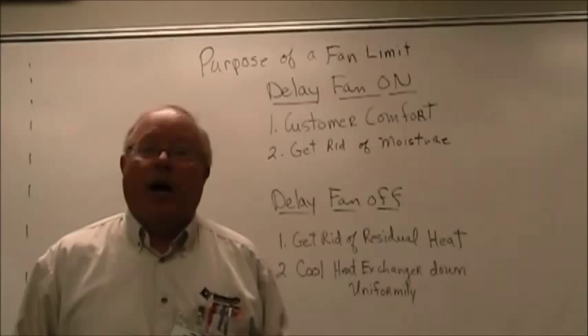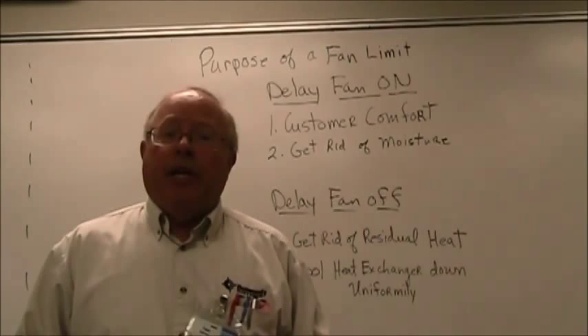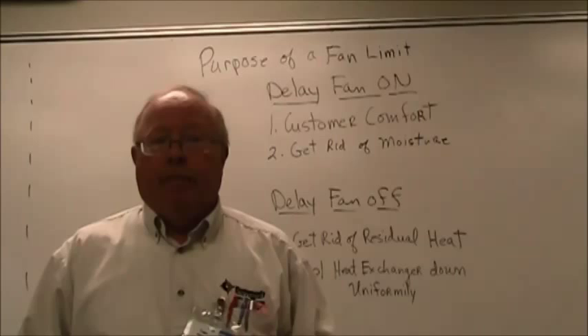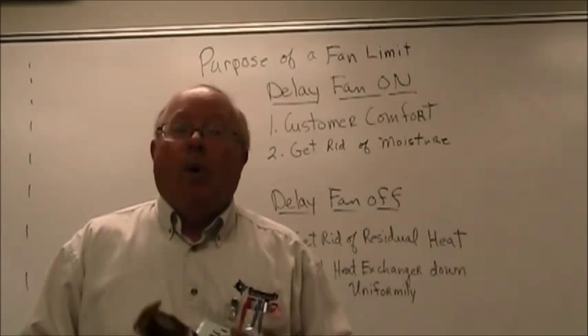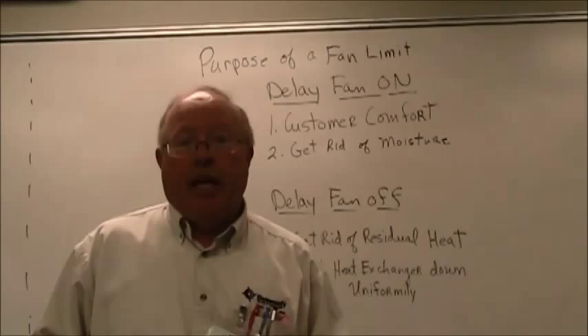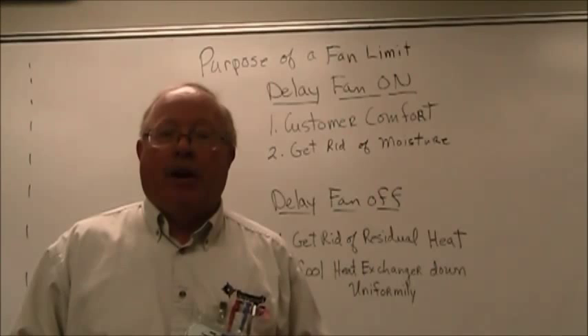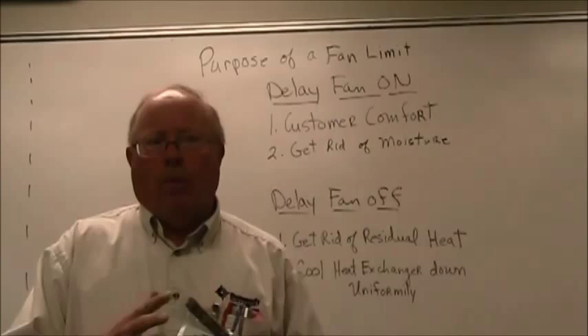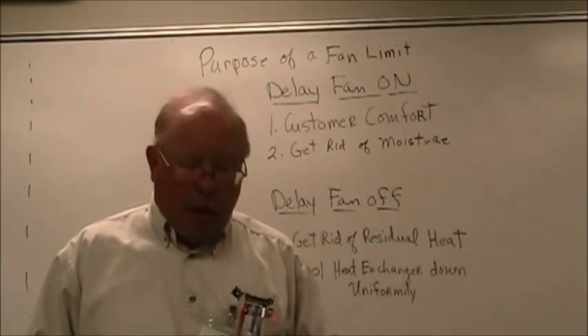The next reason is I want to cool the heat exchanger down uniformly. The heat exchanger is made out of metal, and being metal, it's going to have the thermal coefficients of expansion — the metals are going to expand and contract. In order to stop work hardening and metal fatigue, we're going to cool that heat exchanger down in a uniform manner with air going across it. That way, the heat exchanger will not crack, it won't buckle, and those seams on it won't be compromised.